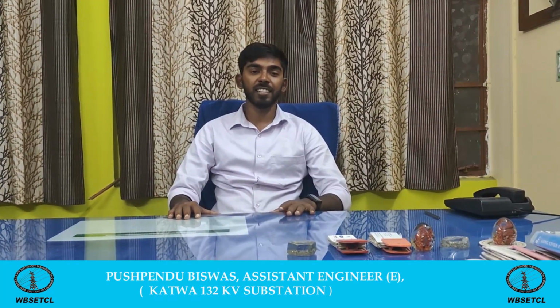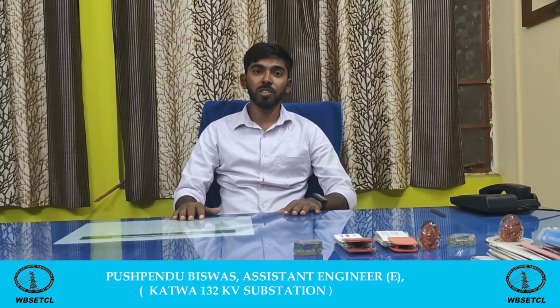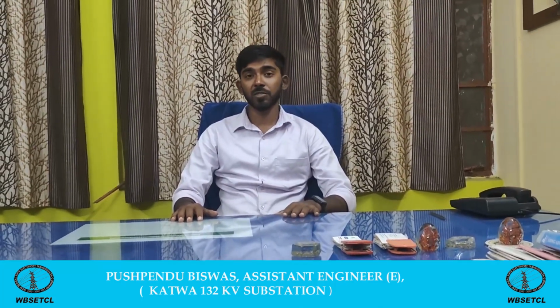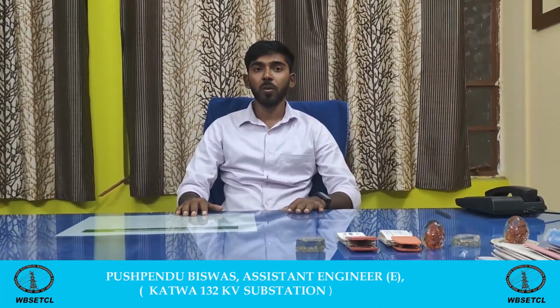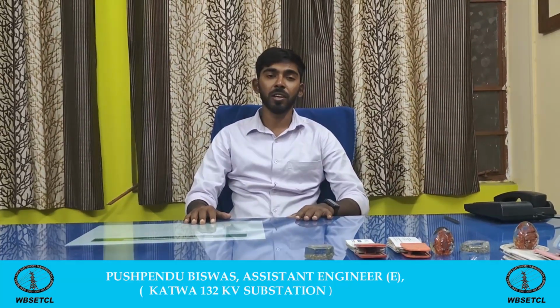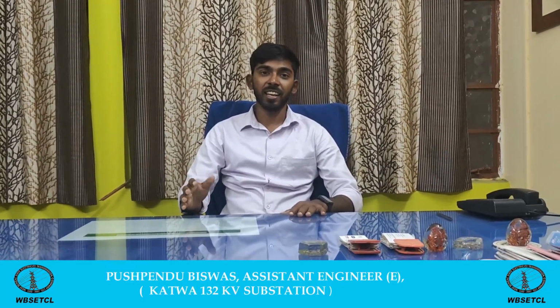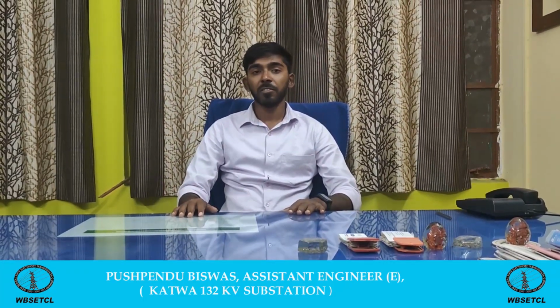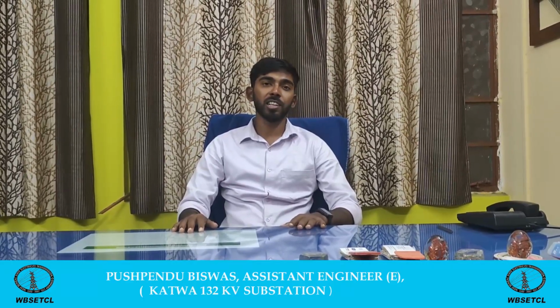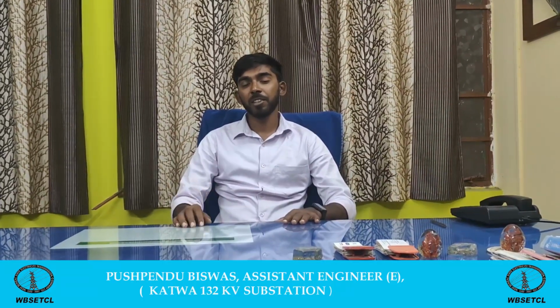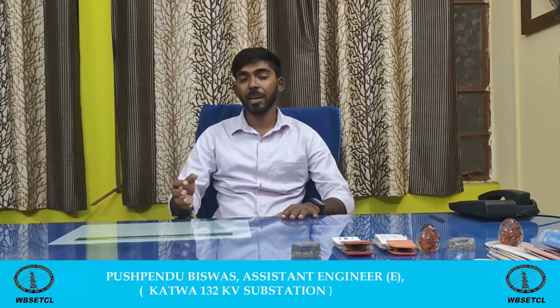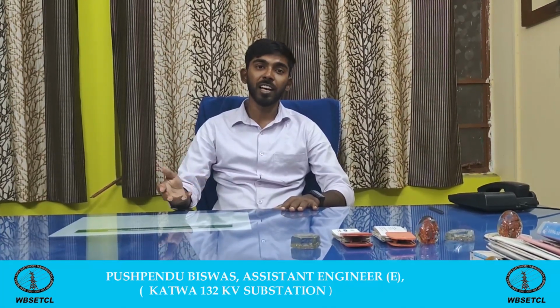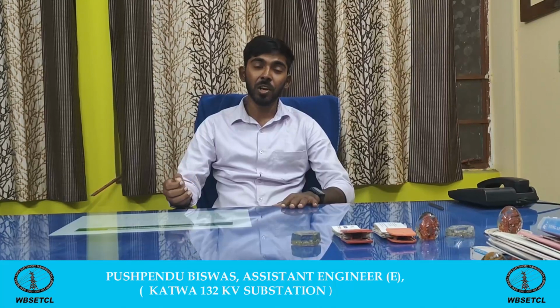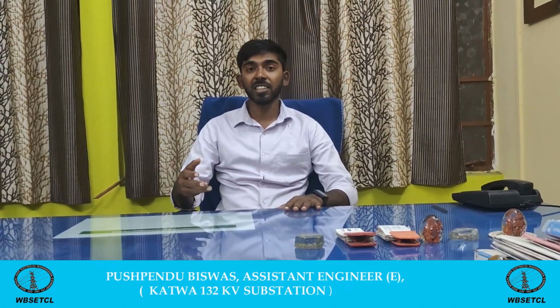In the year 1989, this substation was commissioned by charging a single 20 MVA transformer to cater 33 kV. Over the years, this substation has undergone massive challenges and hence upgradations were made in the system gradually. For example, 3 numbers of 31.5 MVA transformers were replaced by 3 numbers of 50 MVA transformers to enhance the capacity of the substation. It was done in the year 2019. In the following year, a second set of battery bank and battery charger was installed so as to provide redundancy in the DC system.